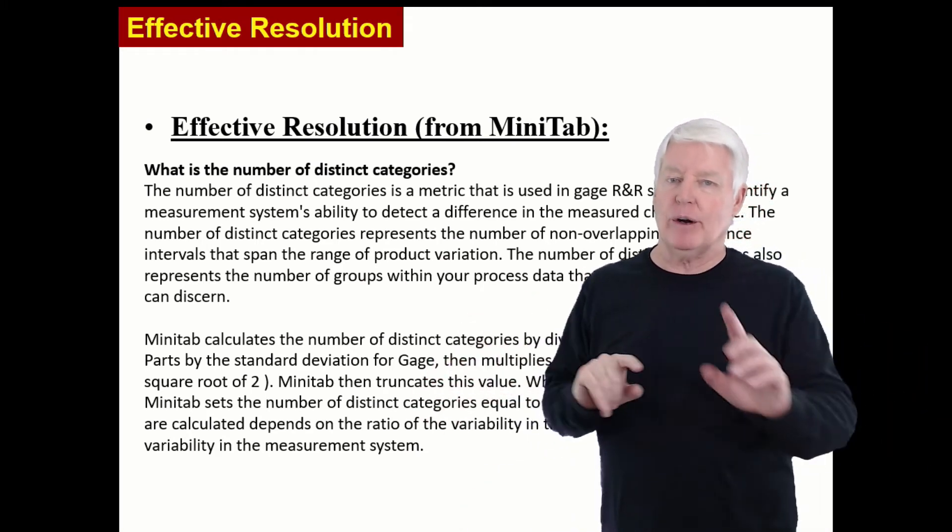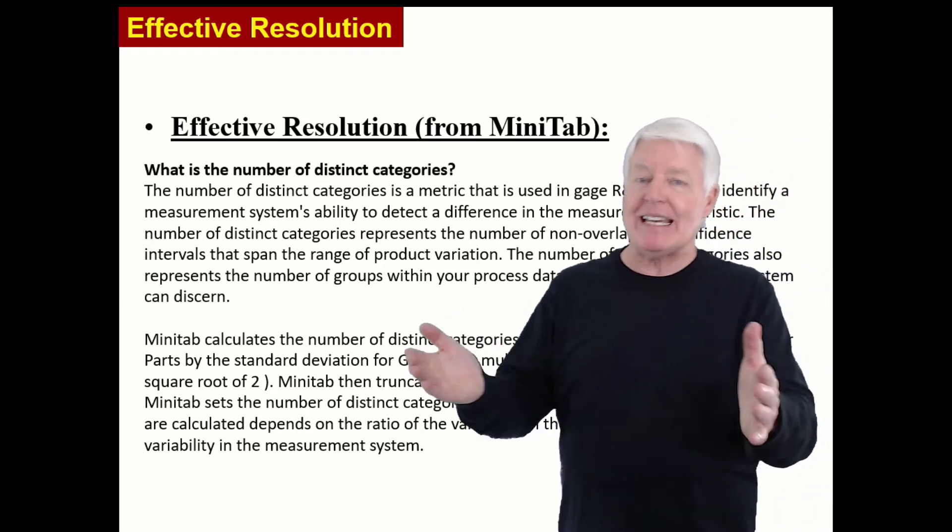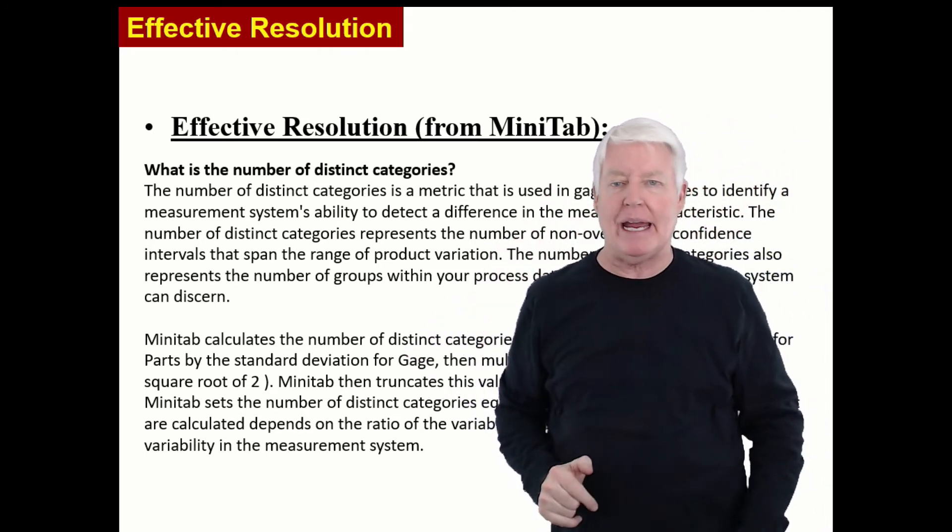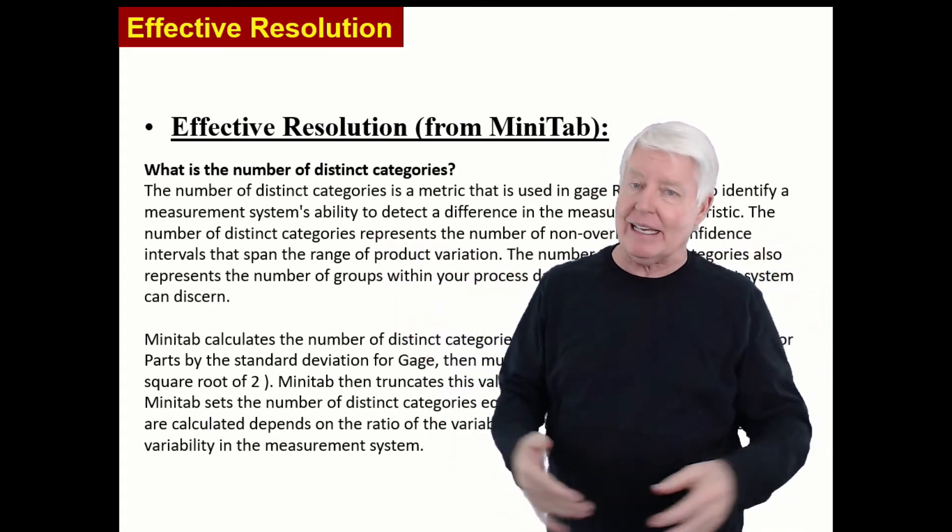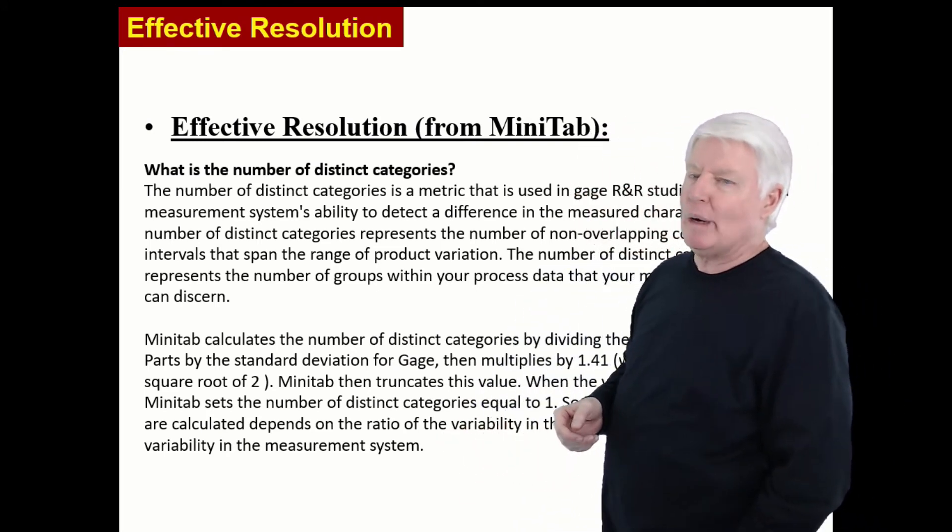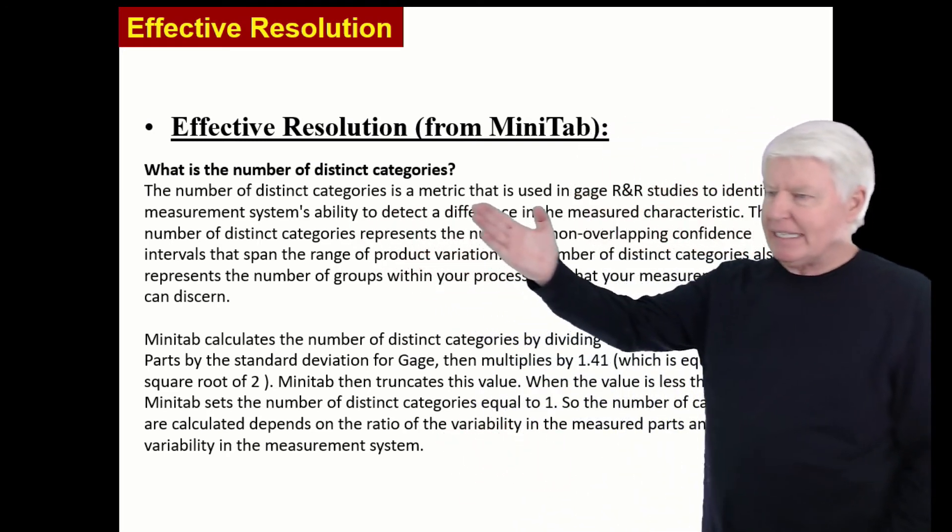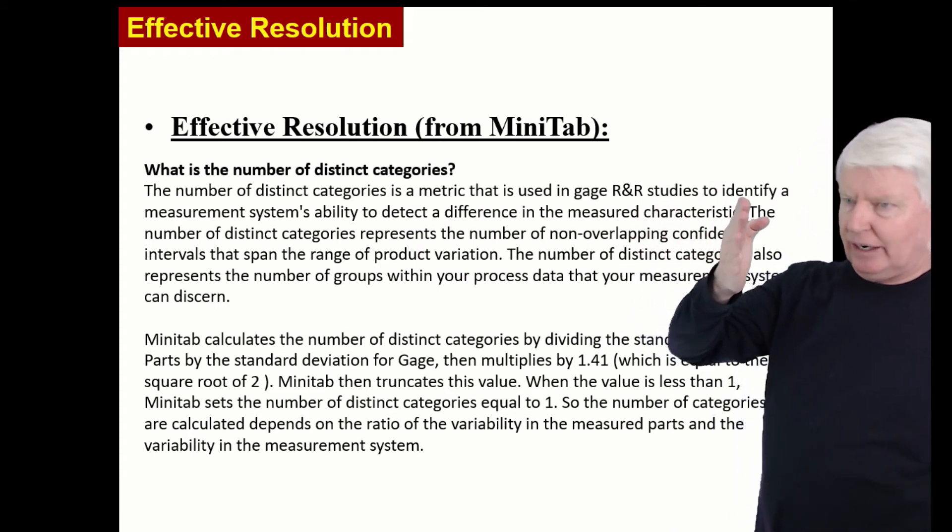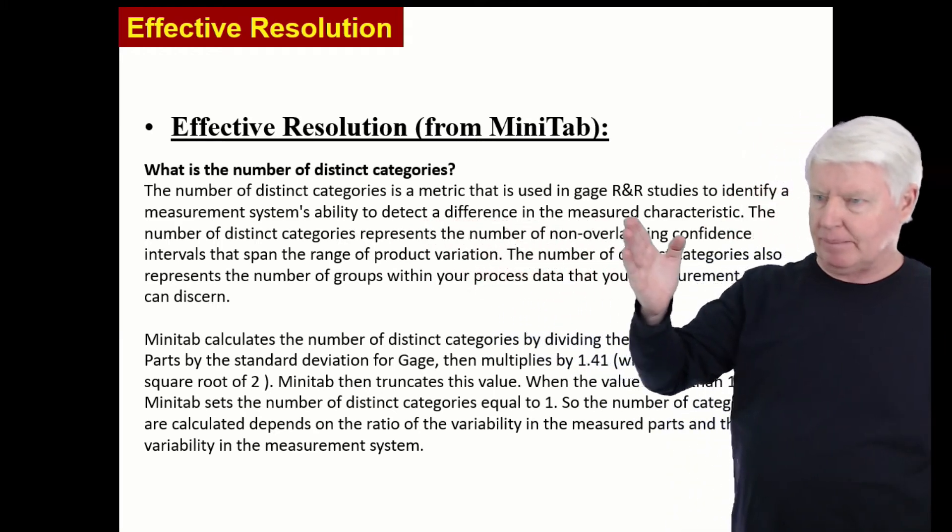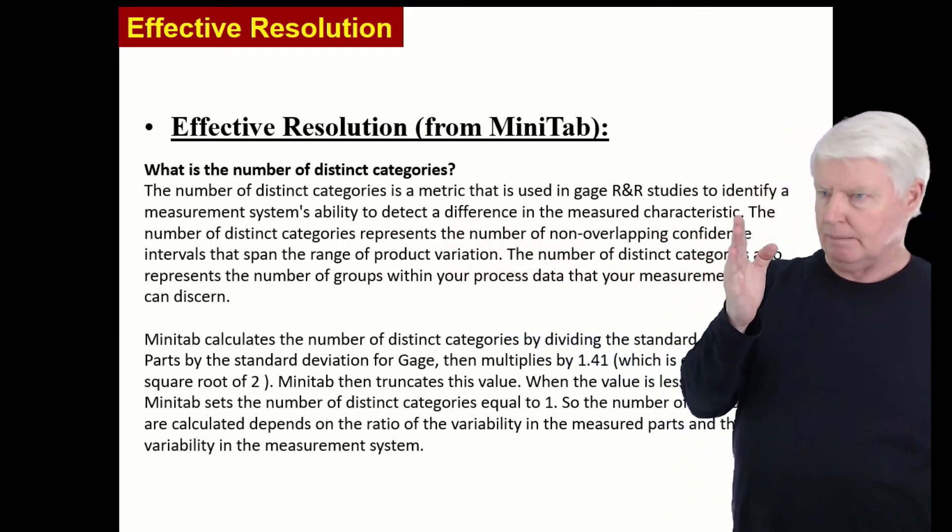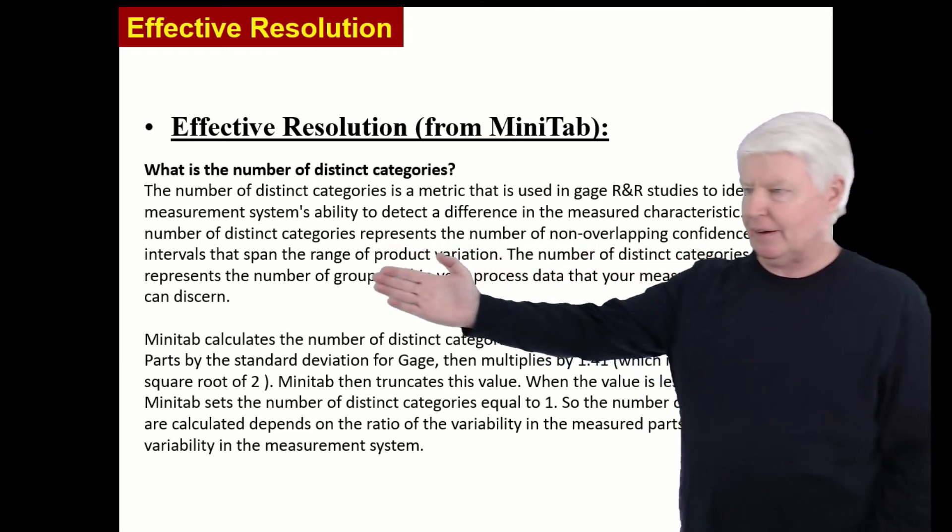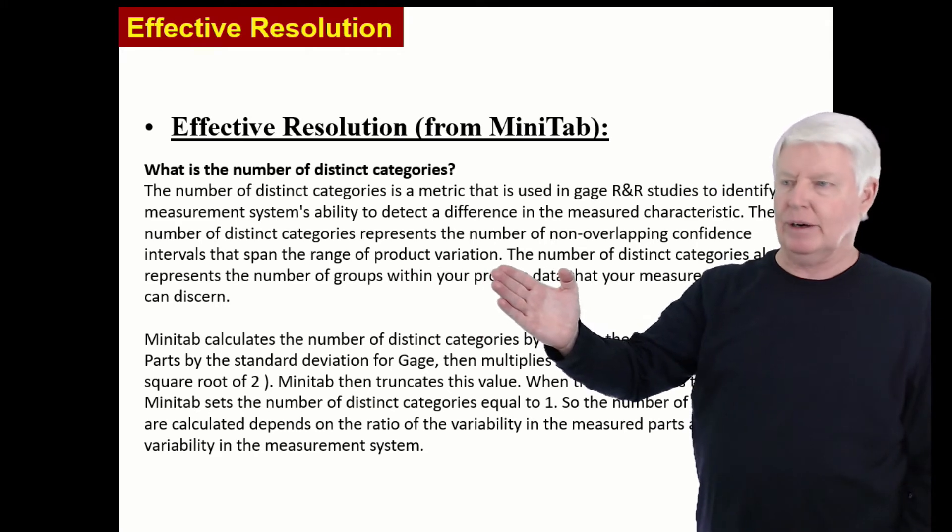So what is the number of distinct categories or NDC? Remember, we like NDC of five or greater. And you can think of it this way. This is the easiest way is how many columns does your measurement system create on the histogram. If it's five, that's the number of distinct categories is five. So that's the easiest way. But now we're going to get into the weeds a little deeper. The number of distinct categories is a metric that is used in gauge R&R studies to identify a measurement system's ability to detect a difference in the measured characteristic.